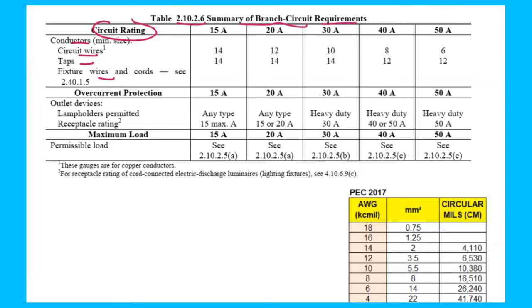Sa 15 ampere circuit breaker, dapat choose this row, this circuit wires. Okay, so ang 20 ampere, ang circuit wires nila is dapat number 12. Ito number 12. So if you look on the PEC 2017, ito yung table na ginawa ko, summarize. So yung number 12 mo, ang wire niya dapat is 3.5 square mm. So ito is dapat 3.5 square mm.